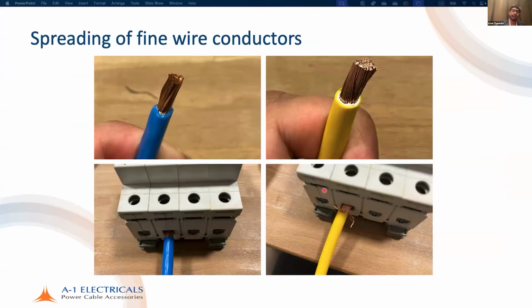Spreading of fine wire conductors is a particular problem in box terminals. For example, when you have a class 2 conductor entering a box terminal, there is no significant spreading, so there is pretty good electrical continuity and mechanical strength. Class 5 conductors tend to spread quite a bit. So this is a particular problem that we have in class 5 conductors when we enter a box terminal.